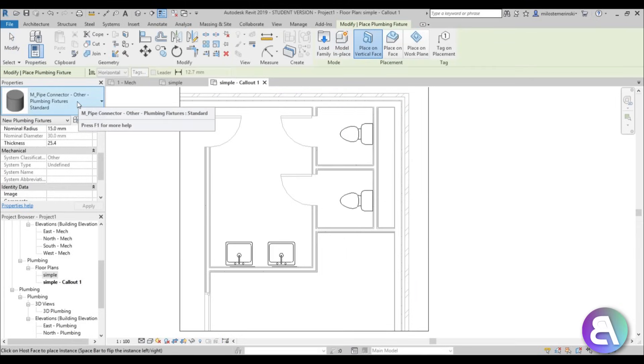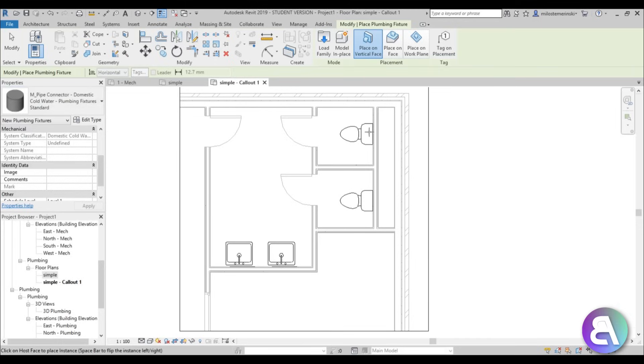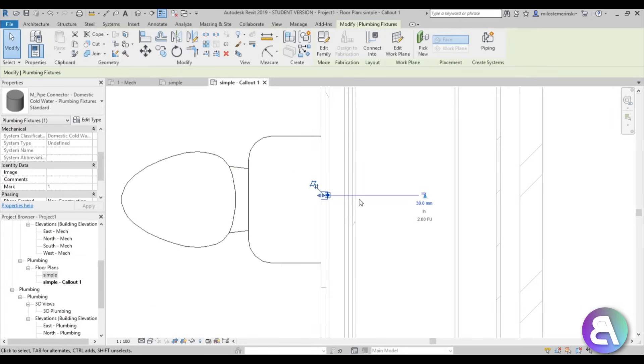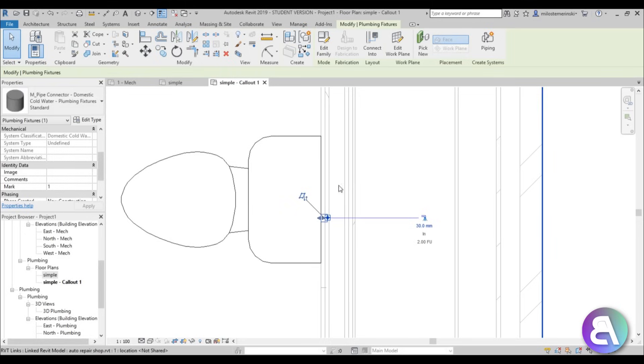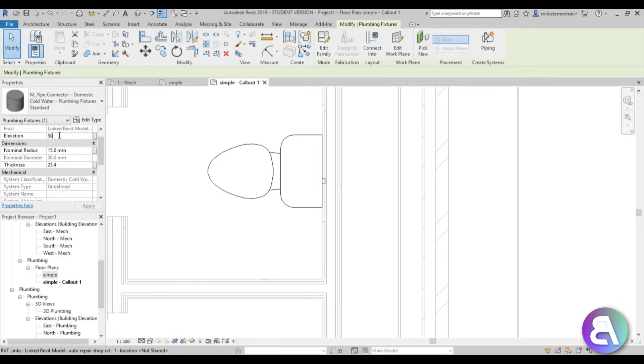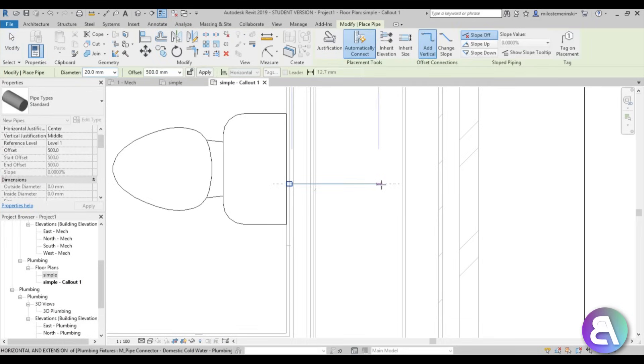Go back to the Systems tab, find Plumbing Fixture, and open it up. Select the Domestic Cold Water connector — since this is a water closet, we only need cold water. Make sure 'Place on Face' is selected, then zoom in and place the connector on the wall face. If you can't see it clearly, switch to Wireframe. Move it slightly to the right of the toilet to leave room for a second connector later. Set the elevation to 500 mm and the pipe diameter to 20 mm.